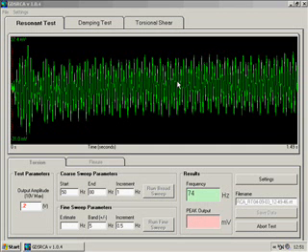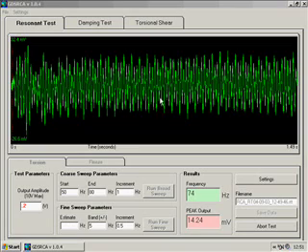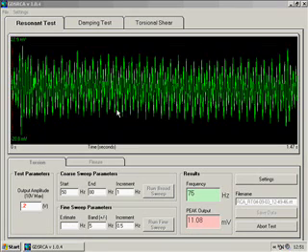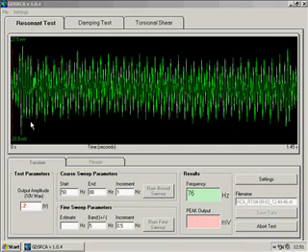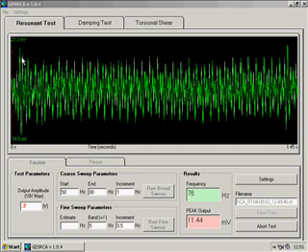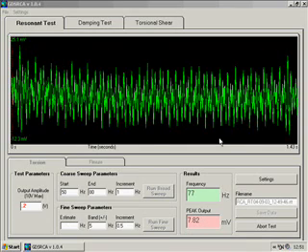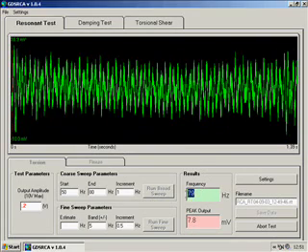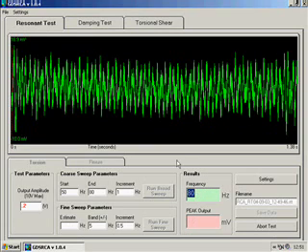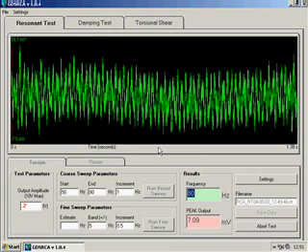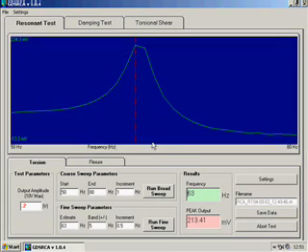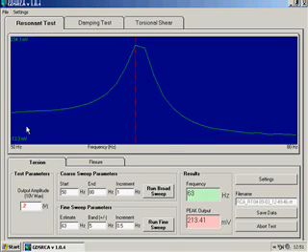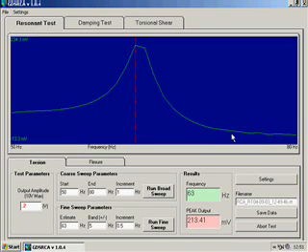As we approach the end frequency of 80 hertz, we can see that the graph is currently displaying the accelerometer output against time. When a frequency of 80 hertz is achieved, the plot of frequency against peak output is plotted for the full range of the broad sweep that we just performed.